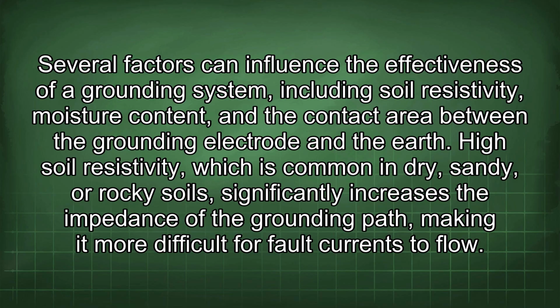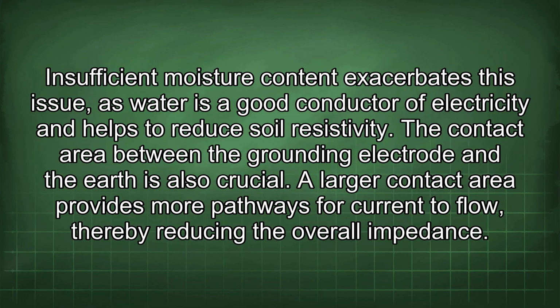High soil resistivity, which is common in dry, sandy, or rocky soils, significantly increases the impedance of the grounding path, making it more difficult for fault currents to flow. Insufficient moisture content exacerbates this issue, as water is a good conductor of electricity and helps to reduce soil resistivity. The contact area between the grounding electrode and the earth is also crucial. A larger contact area provides more pathways for current to flow, thereby reducing the overall impedance.